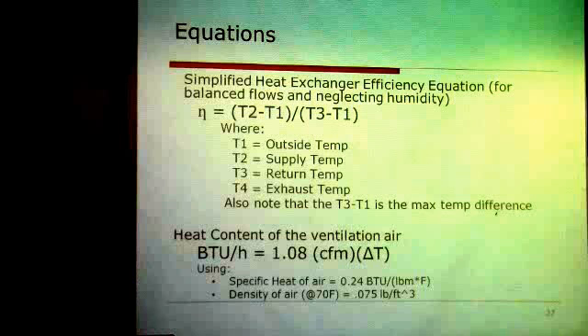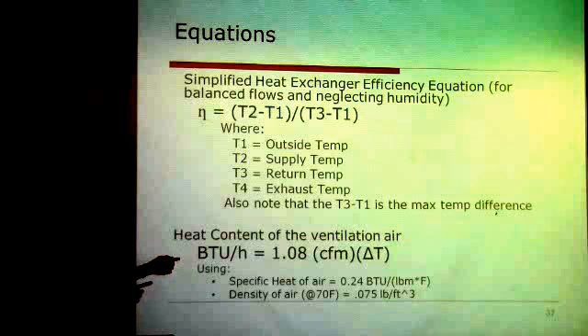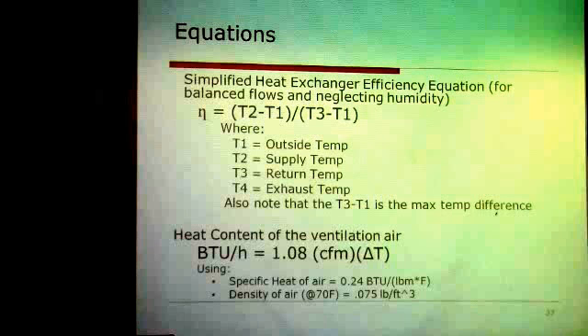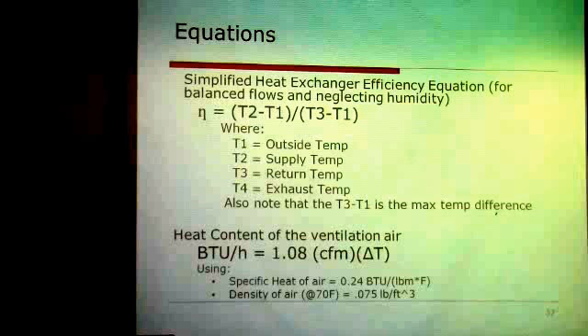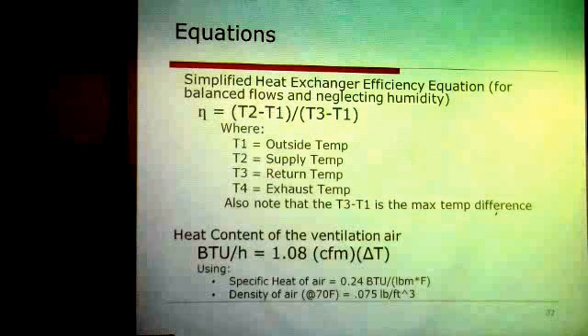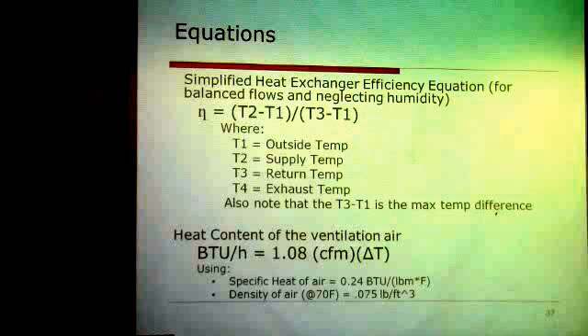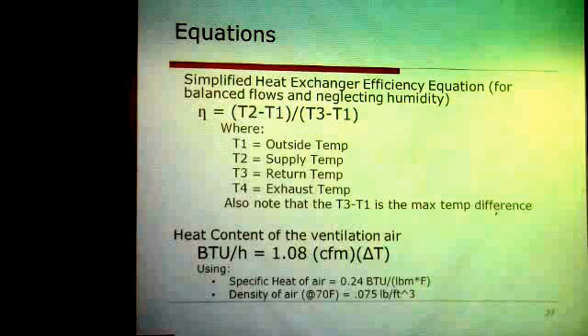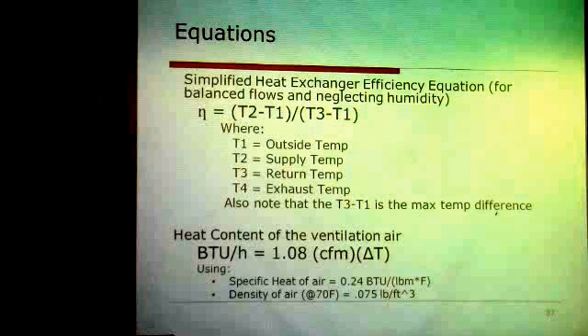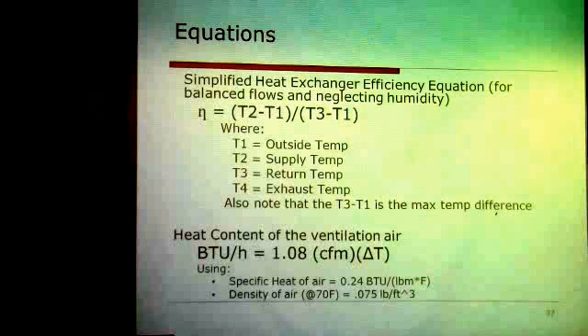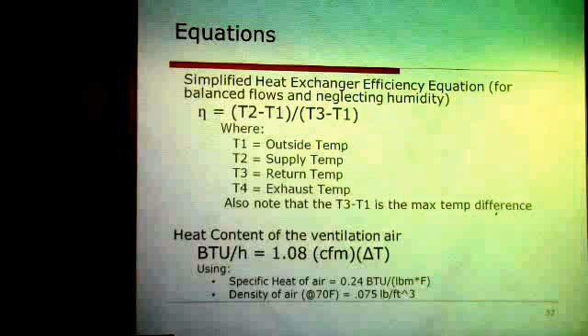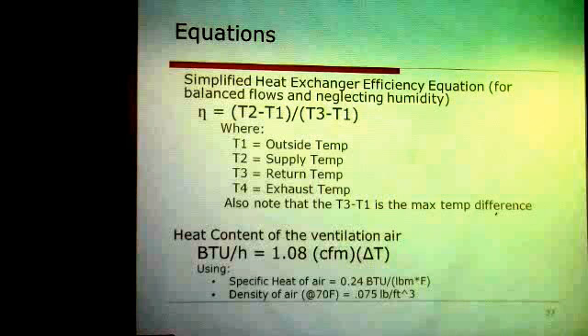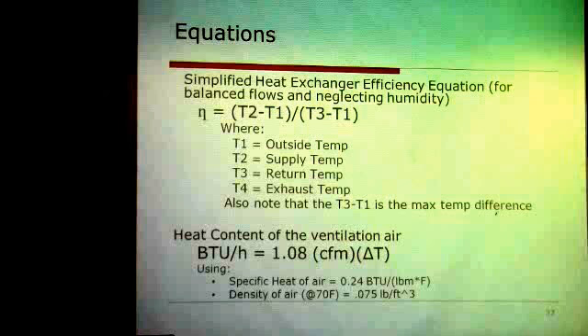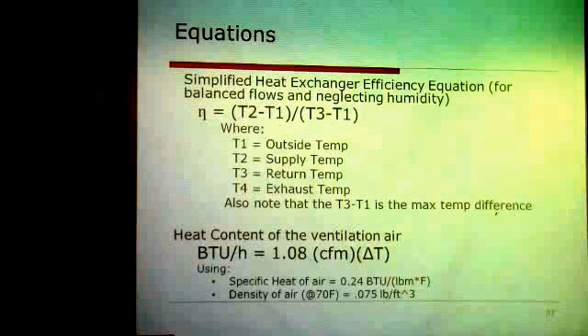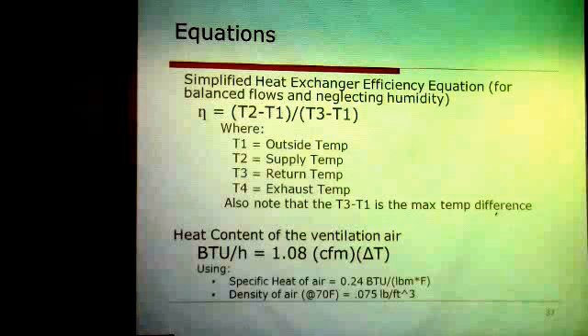At 60 CFM, or say 100 CFM, say you have a bigger house, maybe 2,500 square foot, and you need 100 CFM continuous. So that 55 times 100 is 5,500 BTUs times 1.08. So you're close to around 6,000 BTUs, and that's all the heat you can carry. So if your heating load is more than 6,000 BTUs, you won't be able to heat on that ventilation air. So there's very few times you can do that. You hear about people trying to, but if you bump up the airflow to get the heat to the house, you start overventilating, and then you have to make sure you're getting the air to the right place, and equalize it.